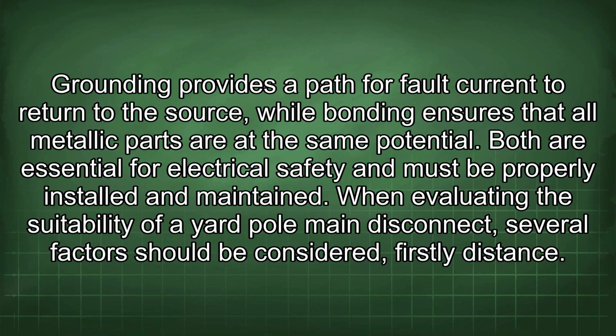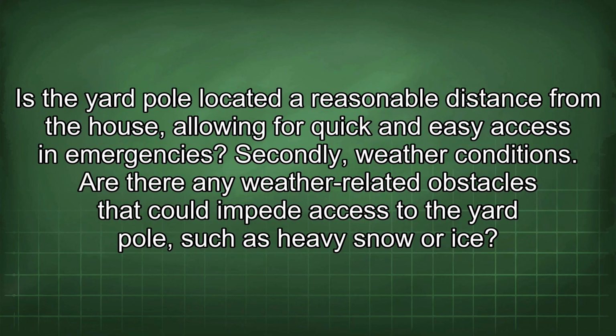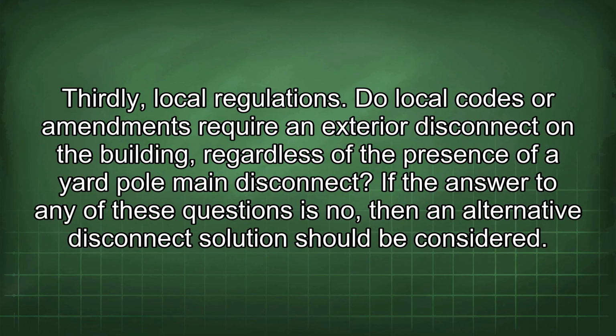When evaluating the suitability of a yard pole main disconnect, several factors should be considered. Firstly, distance. Is the yard pole located a reasonable distance from the house, allowing for quick and easy access in emergencies? Secondly, weather conditions. Are there any weather-related obstacles that could impede access to the yard pole, such as heavy snow or ice? Thirdly, local regulations. Do local codes or amendments require an exterior disconnect on the building regardless of the presence of a yard pole main disconnect? If the answer to any of these questions is no, then an alternative disconnect solution should be considered.